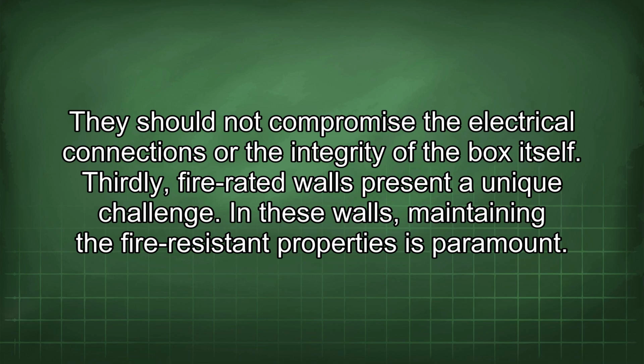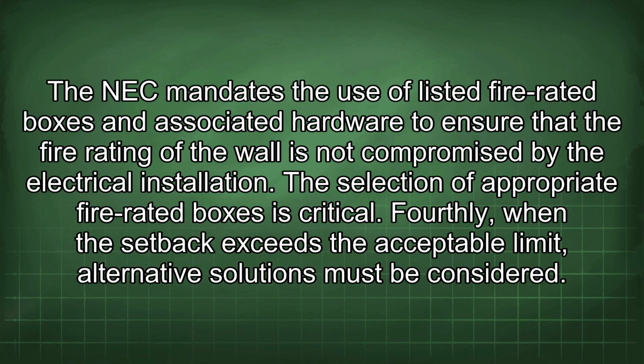Thirdly, fire-rated walls present a unique challenge. In these walls, maintaining the fire-resistant properties is paramount. The NEC mandates the use of listed fire-rated boxes and associated hardware to ensure that the fire rating of the wall is not compromised by the electrical installation. The selection of appropriate fire-rated boxes is critical.